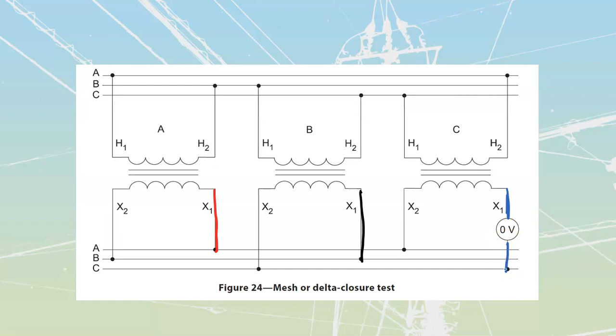If I take a look, I've got additive transformers going across. My X1 of A goes over here, my X1 of B goes to my B line, and my X1 of C we're stopping for the time being, but it should go all the way down to C. Then I'll do the opposite side: my A transformer's X2 goes down to B, my B transformer's X2 goes down to C, and my C transformer's X2 goes up to A.